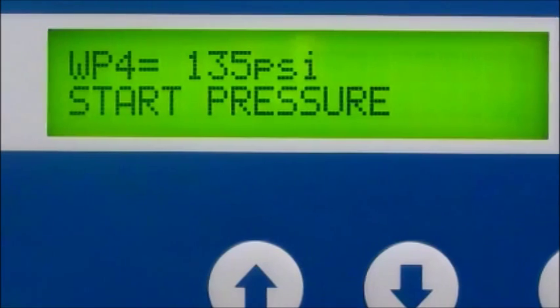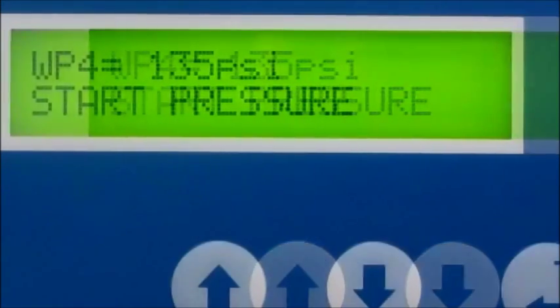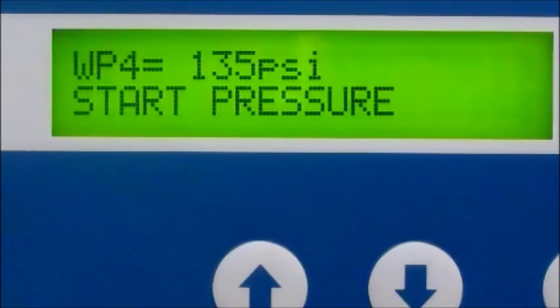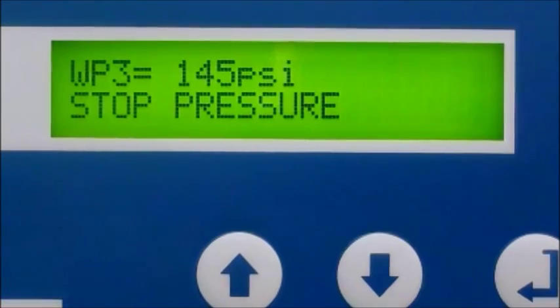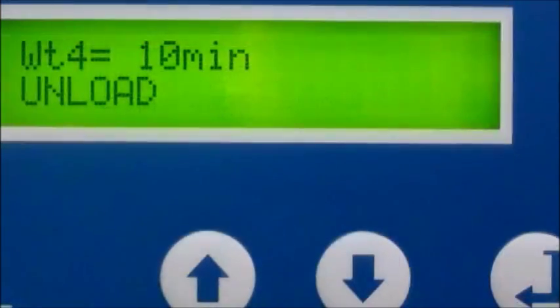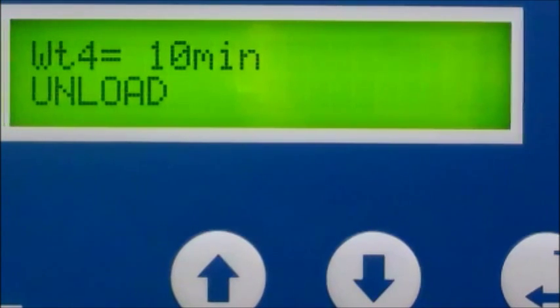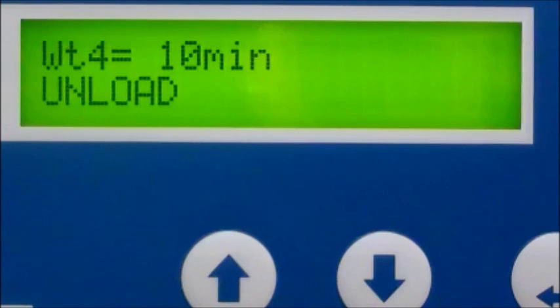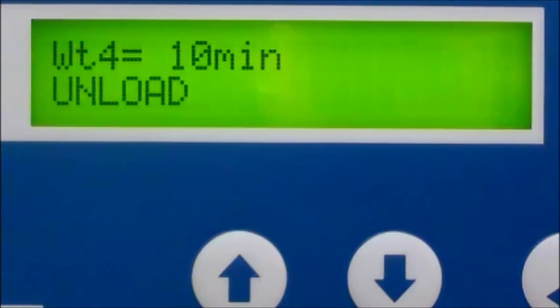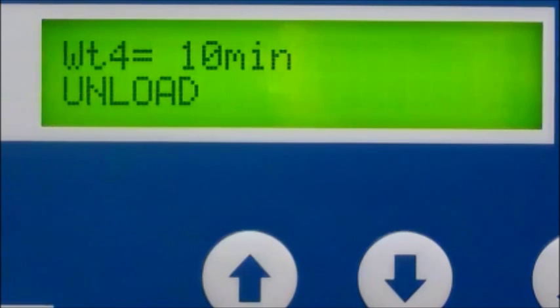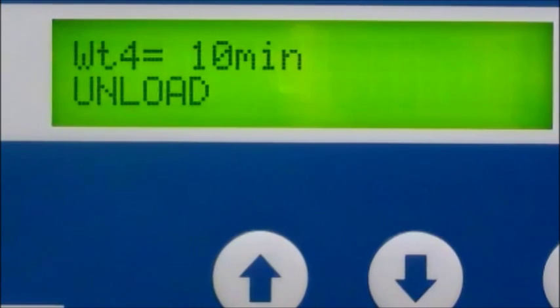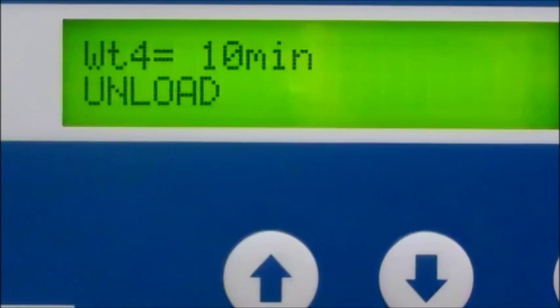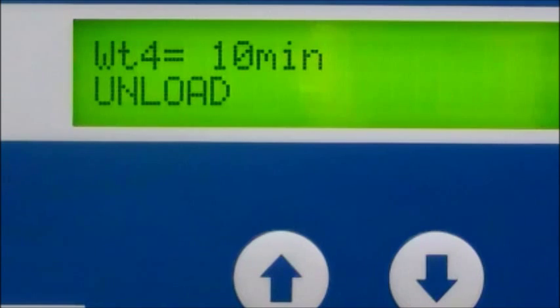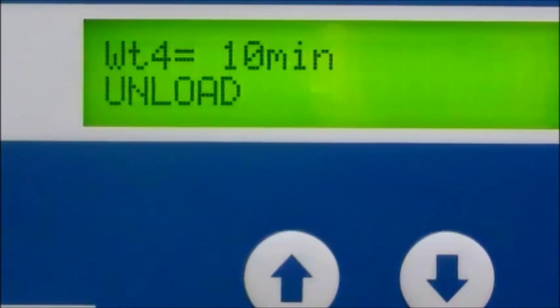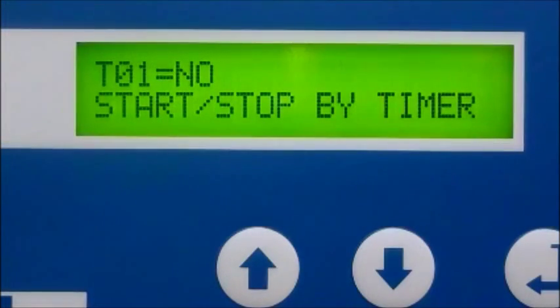The PLC has too many programmable features to cover in this video, so let's examine some of the more popular ones. Pressure ranges can be programmed from 45 psi to 145 psi, permitting you to tailor the compressor's air pressure range to your specific needs. Timed no-load shutdown and restart can be set from 1 minute to 10 minutes. This simply means if set to 10 minutes, the PLC will shut the machine off if the air pressure has remained above the low pressure setting for more than 10 minutes. Of course, the machine will restart when the air pressure drops below the low pressure setting. Again, this can be tailored to best fit your needs.